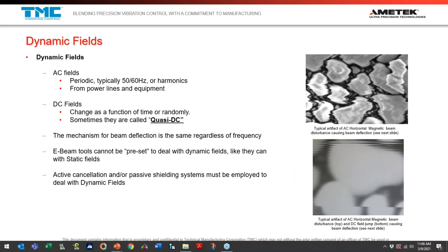Dynamic fields are fields that are changing. AC fields are by nature always changing — the magnitude shifts from one polarity to the negative polarity at 60 times a second. An AC field can have a constant magnitude but it's always changing polarity, which is why we call it a dynamic field. DC fields can also change over time, but a constant DC field is more like a static field. When a DC field starts to change slowly, we use the term 'quasi DC' fields — very slowly changing fields caused by a magnetic object like an elevator, or sometimes a garbage cart or a truck — something ferromagnetic moving through the environment distorting magnetic field lines.